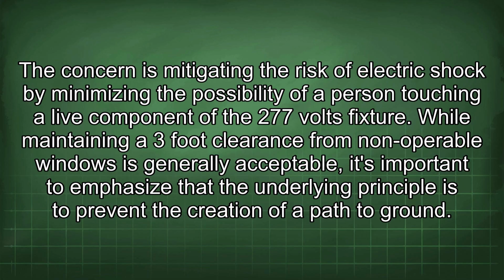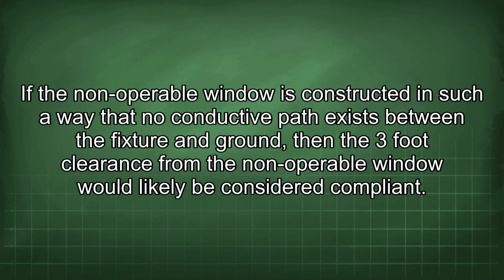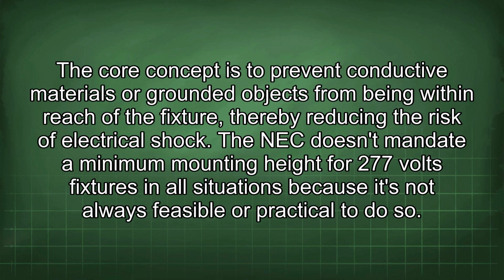While maintaining a 3-foot clearance from non-operable windows is generally acceptable, it's important to emphasize that the underlying principle is to prevent the creation of a path to ground. If the non-operable window is constructed in such a way that no conductive path exists between the fixture and ground, then the 3-foot clearance from the non-operable window would likely be considered compliant. The core concept is to prevent conductive materials or grounded objects from being within reach of the fixture, thereby reducing the risk of electrical shock.